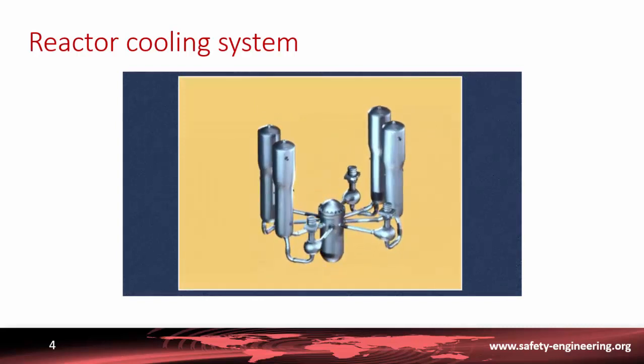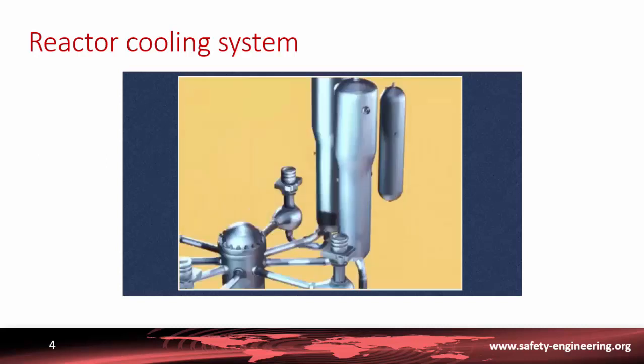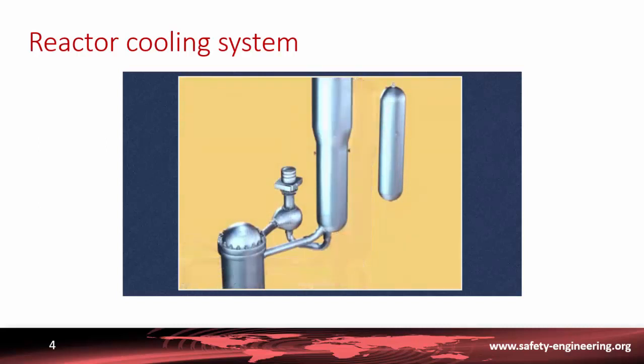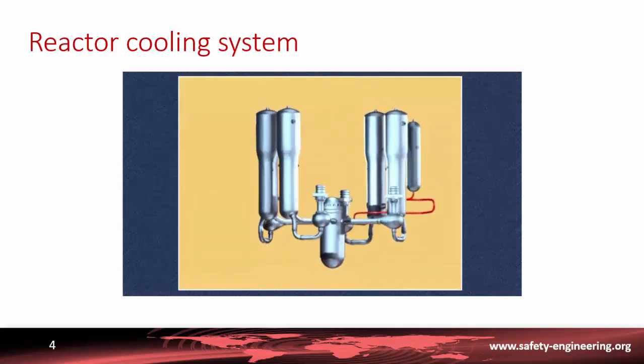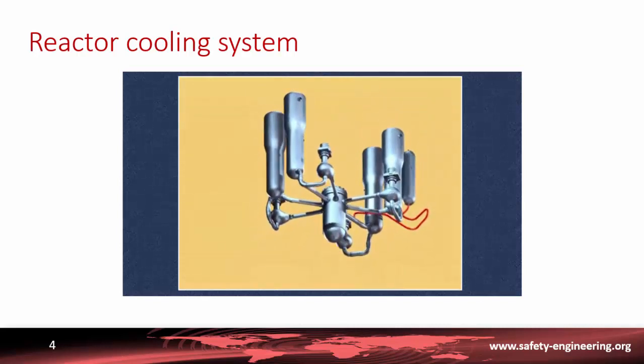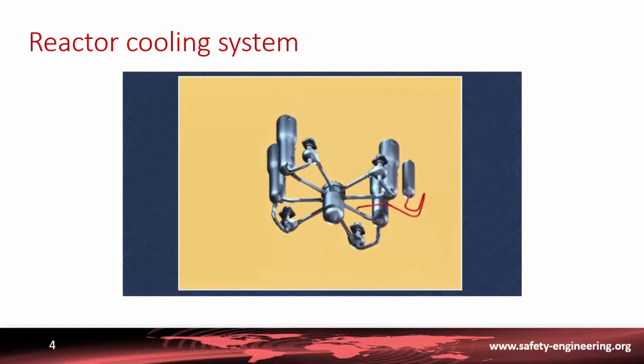To prevent the primary water from boiling, although it is at a temperature of 320 degrees centigrade on leaving the reactor vessel, a pressurizer is provided which maintains high pressure in the system. The bottom of the pressurizer is connected to one of the loops by a pipe which, after a number of expansion bends, joins the hot leg of the loop. This constitutes the pressurizer expansion line. These are the main components of the reactor coolant system.